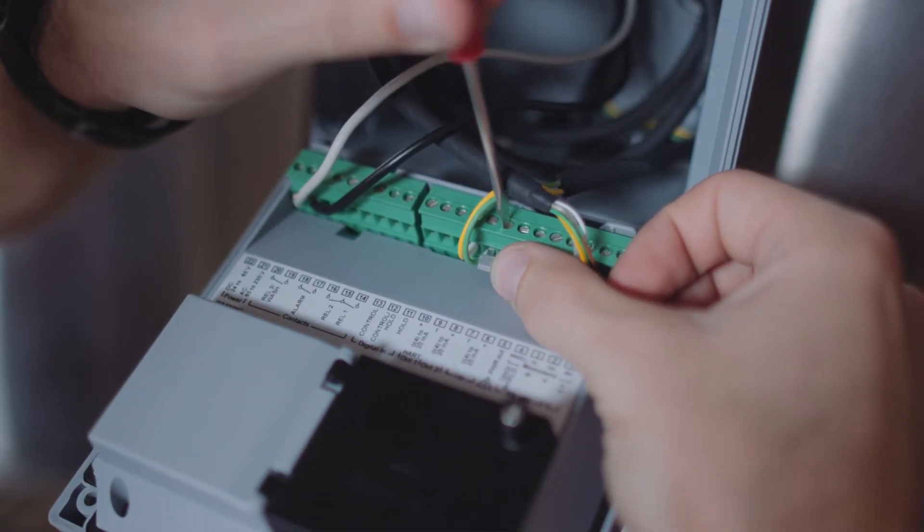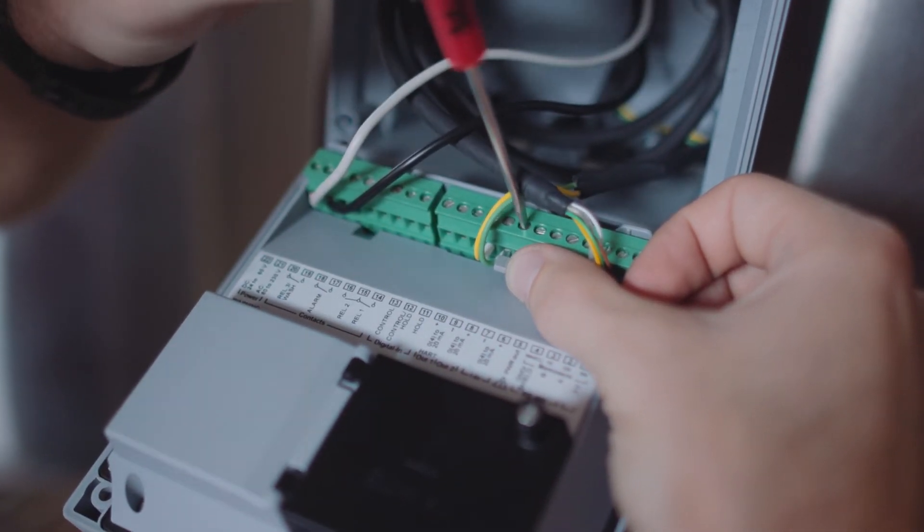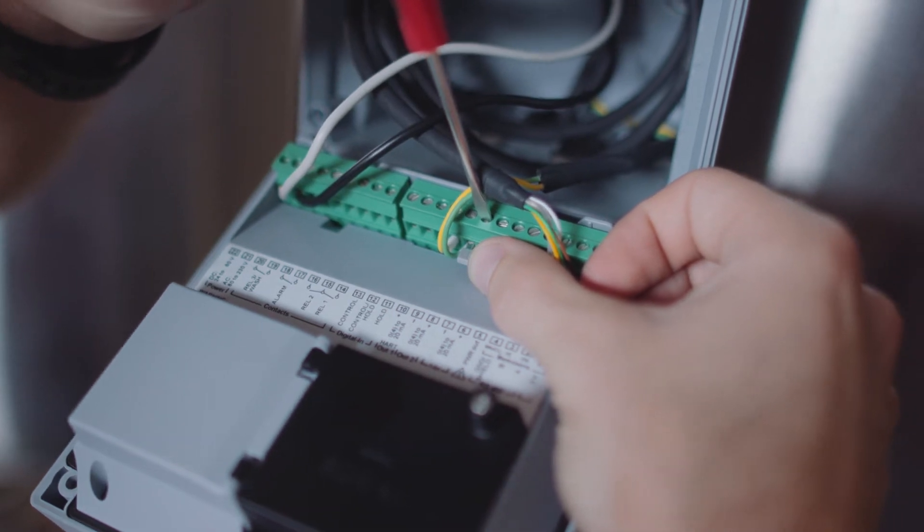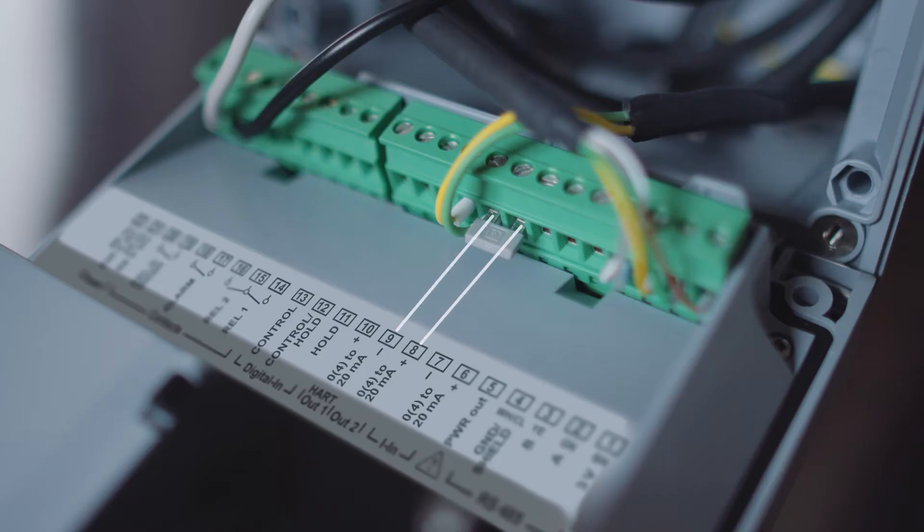If only one of the outputs is being utilized, a jumper can be applied to the second output to rid this error on terminals 8 and 9. Please note that both outputs share terminal 9. Jumpers are included in the accessory bag which is shipped with the transmitter.